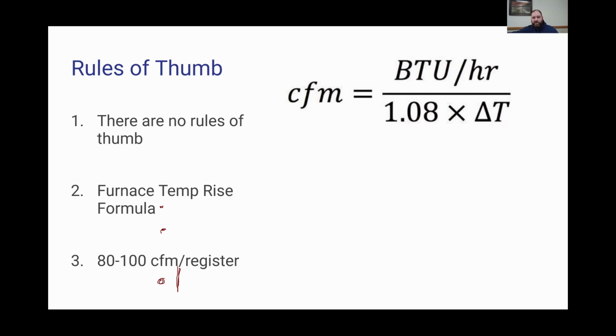One of the key differences between a high efficiency furnace and a low efficiency furnace, or the same thing can be said for an air conditioner or heat pump, is how much air you're getting through the system. Back when we had medium efficiency furnaces, an average home with a 60 to 80,000 BTU furnace was looking for between 650 and 850 CFM. Nowadays, that same furnace will run with 850, but most of them, when you do the calculation, would prefer to be in that 1,000 to 1,200 CFM. So we're talking about moving a third again more air through it.